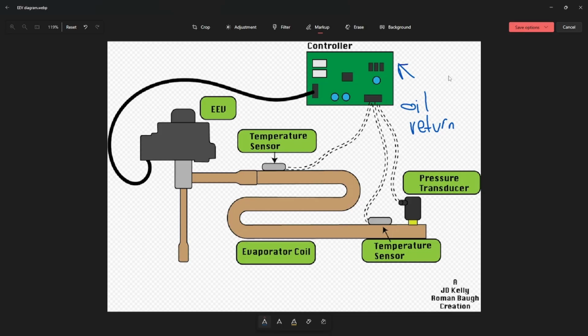Some systems will not stop a cooling call for oil return mode, but Trane does, because Trane values their compressors. I don't know as much information on Carrier inverter driven systems. Rheem does not stop their cooling calls. Rheem will run it to complete the call and then immediately go into oil return mode as soon as the call is done. And the old school Rheem thermostats would actually have a display status code for oil return mode if it was running in oil return mode too much.